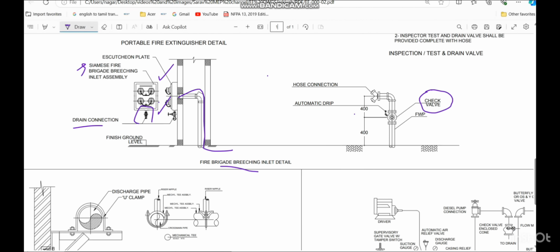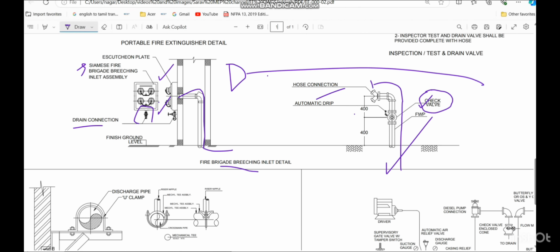And the second important issue normally comes to our mind. We have the check valve, but what is the distance we have to provide? Like from the breaching inlet, can I provide it at 200 mm or 1 meter or 3 meters? What is the rule as per NFPA 13? NFPA 13 explains that the check valve has to be provided as near as possible to the breaching inlet. It's not like the breaching inlet is here and you are providing a check valve 15 meters away. That is not the correct way of installation. You have to provide the check valve as near as possible to the breaching inlet.